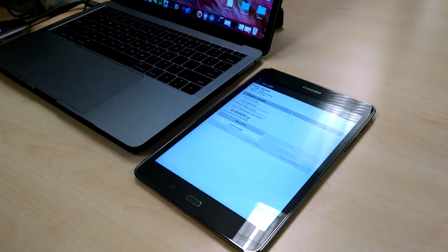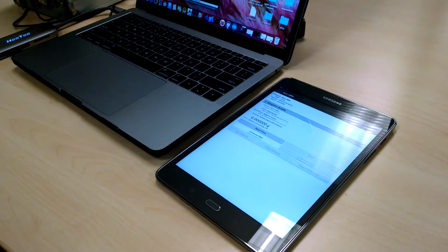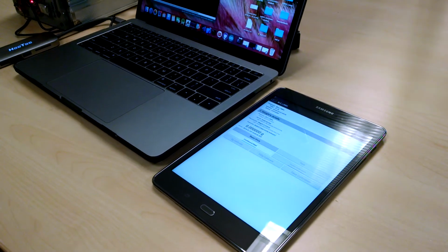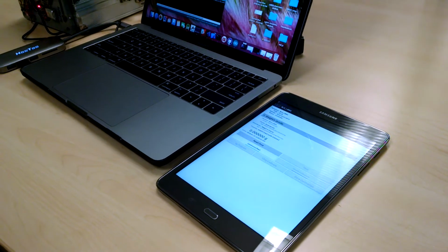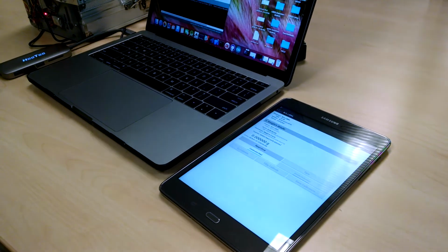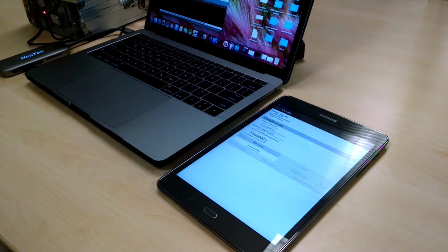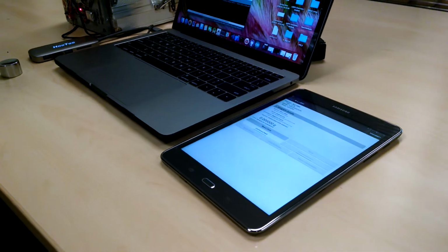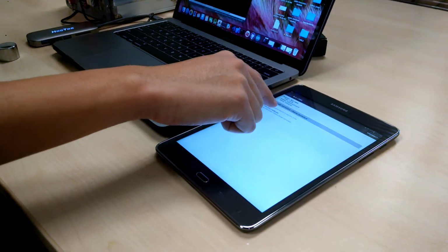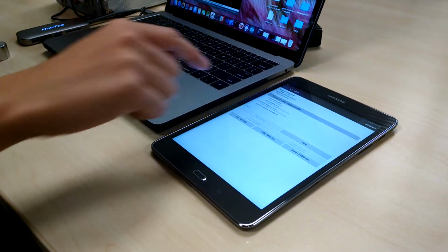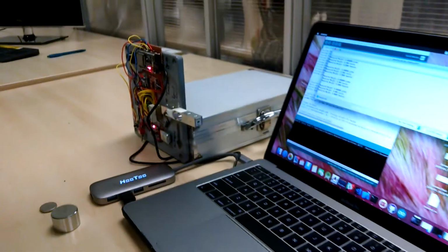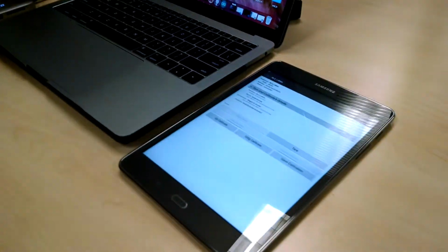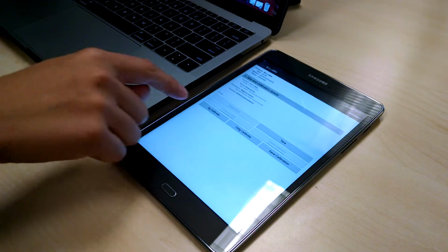also zero. Now, if the scale shifts off of calibration, a two-point calibration function is also programmed into this application. To demonstrate this, we are going to go through the calibration process. The first step in calibration is to measure the value of no weight, of a zero value, of 0 grams.